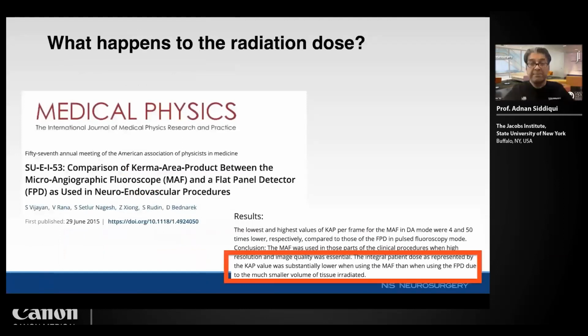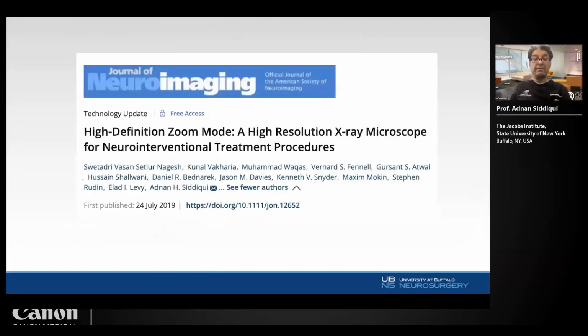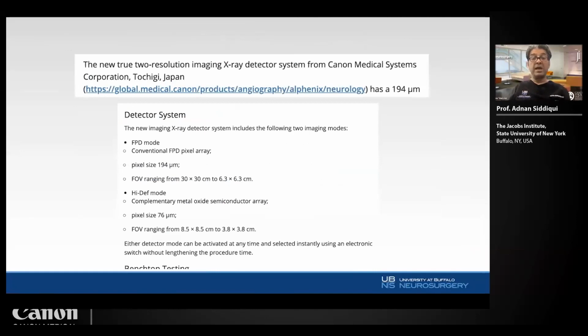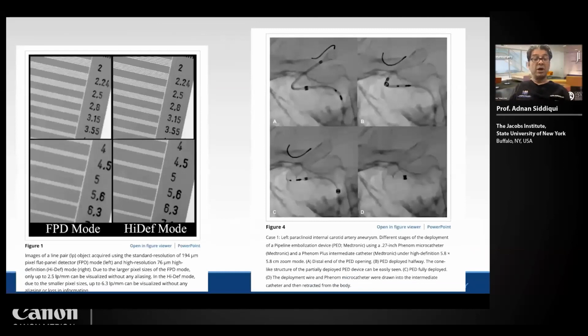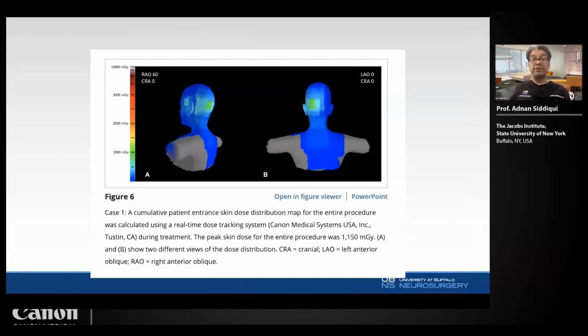So the question then became, well, what happens to the radiation dose? That was the first thing. You must be radiating them. So the point is that when you have the integral patient dose based on the KAP value, it's a lot lower because of the much smaller volume which is being irradiated. And so the best example for this is that it is a high resolution X-ray microscope, just like the one I have in the operating room. And this really can make it quite unique, where you have pixel size compared to a flat panel of 194 down to a 75 micron resolution. That gives you a lot more detail that you would not be able to otherwise garner. And the radiation dose becomes a lot better based on the fact that you're going for a much smaller area than you would otherwise.